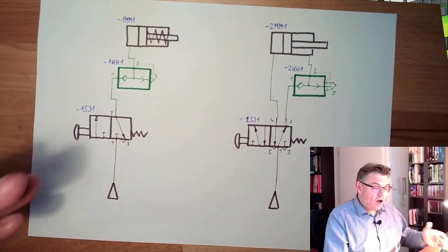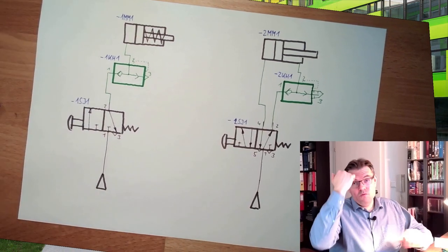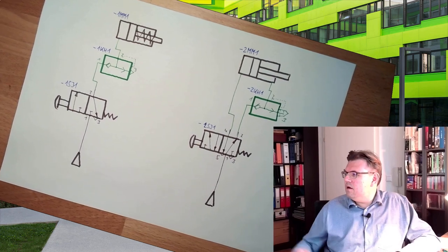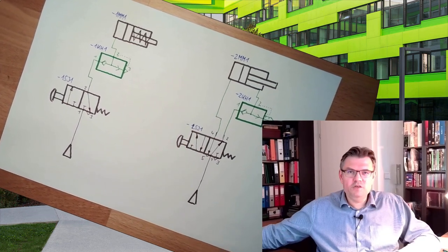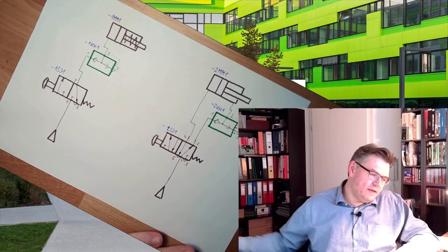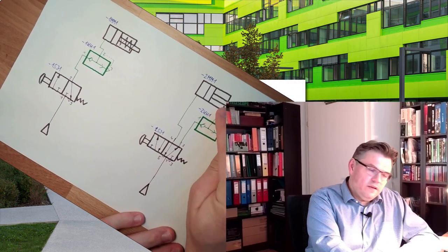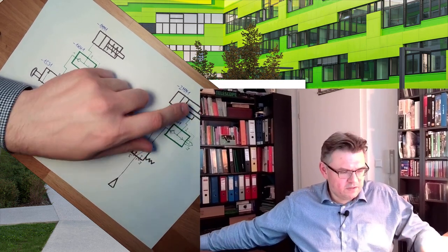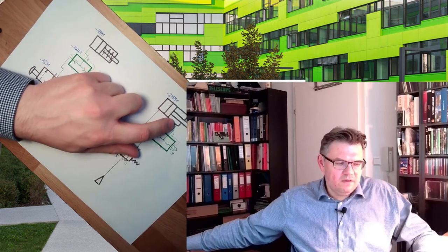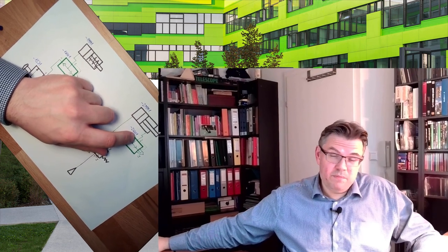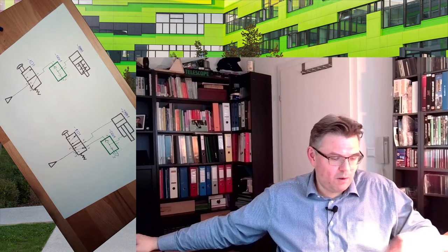This is how you may use quick exhaust valves. Simply to reach the end position, to speed up. And like I said, directly connected to the cylinder, or maybe with a short hose, this is enough. Because the longer the way between the exhaust opening of the cylinder and the quick exhaust valve will be, the more we have troubles.